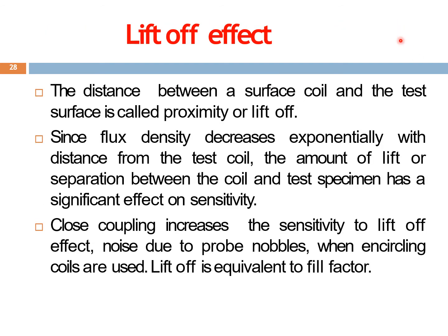Now, what is known as the lift-off effect? Lift-off is the distance between the surface coil and the test surface.